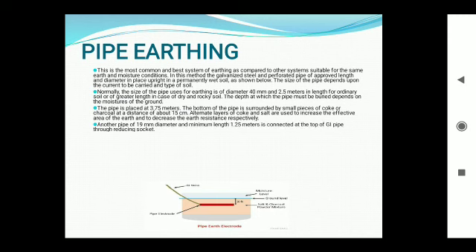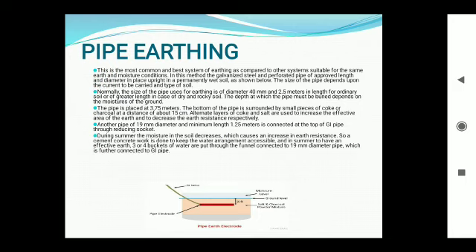Another pipe of 19 mm diameter and minimum length of 1.25 meter is connected at the top of the GI pipe through a reducing socket. During summer, the moisture in the soil decreases, which causes an increase in earth resistance. So, a cement concrete work is done to keep the water arrangement accessible. And in summer, to have an effective earth, 3 or 4 buckets of water are put through the funnel connected to the 19 mm diameter pipe, which is further connected to the GI pipe.